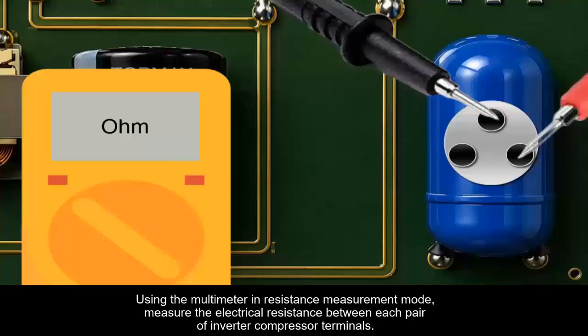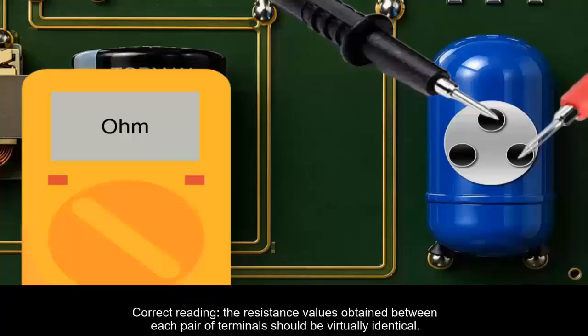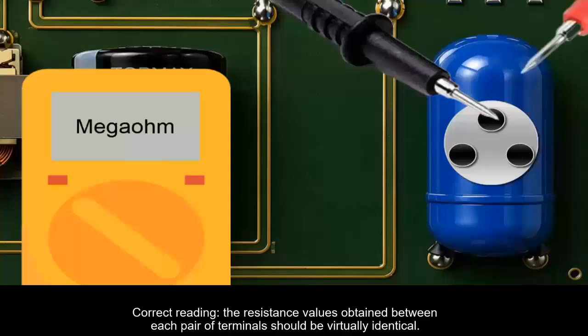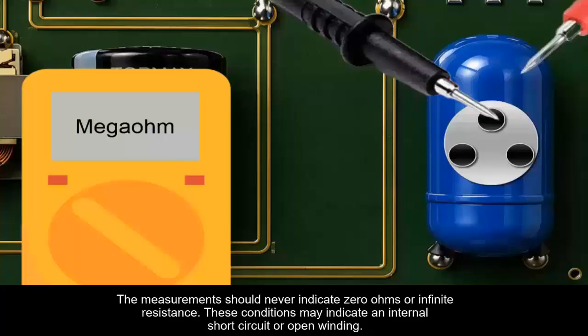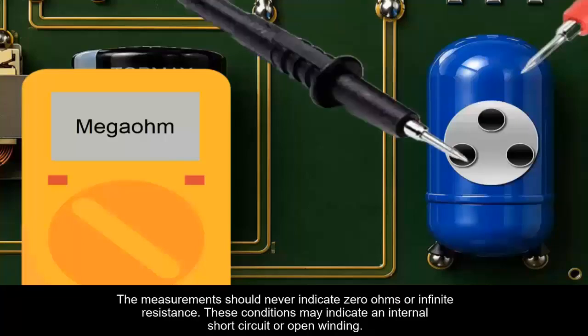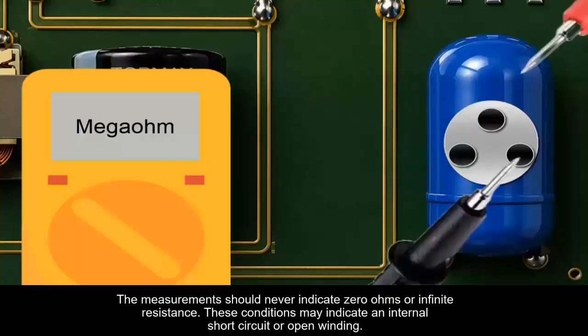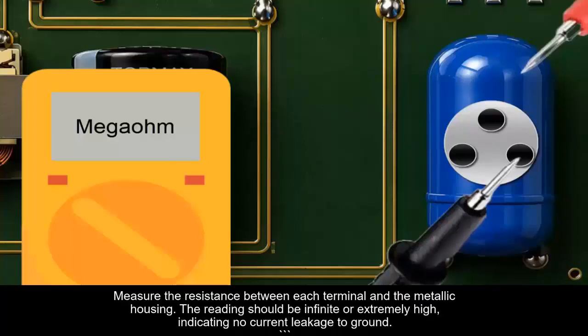Next, using the multimeter in mega-ohm measurement mode or insulation test mode, measure the electrical resistance between each terminal and the metallic housing of the inverter compressor. Correct reading: in all measurements, the value indicated by the multimeter should be infinite or extremely high, indicating that there is no current leakage to ground. If any measurement shows continuity or low resistance between the terminals and the metallic housing of the inverter compressor, this indicates a possible ground fault or damage to the internal insulation of the inverter compressor.